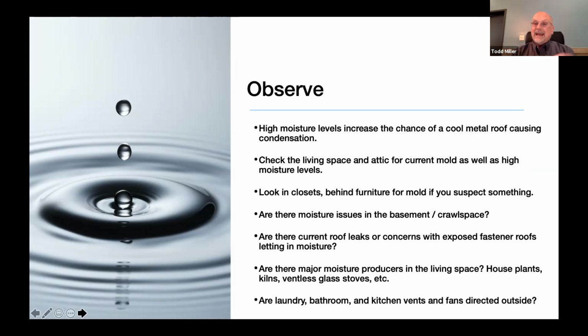And so what was happening was those attic vents, the exhaust vents, were starved for air. They were trying to pull air from every place they could. And they were literally pulling air in through the loose side walls of the home, which was pulling moisture in through those walls that was then getting trapped behind the furniture, leading to the mildew and the mold and the condensation problems behind the furniture on their outside walls.